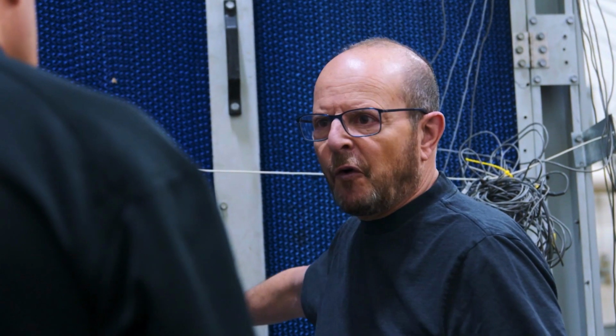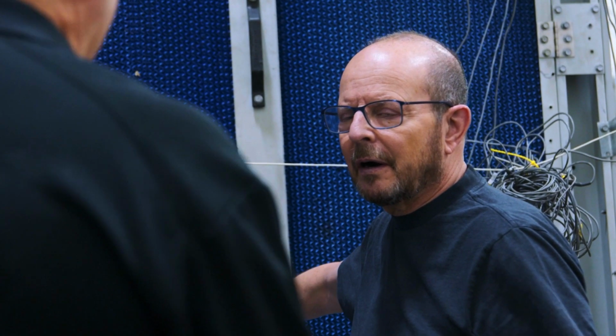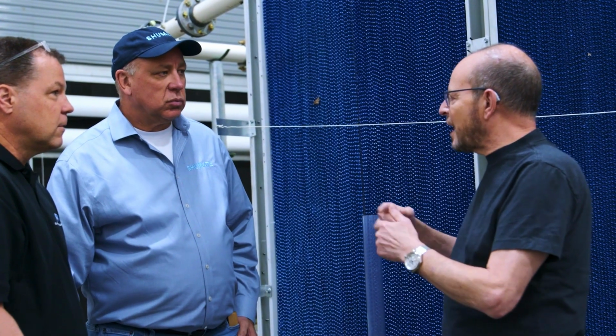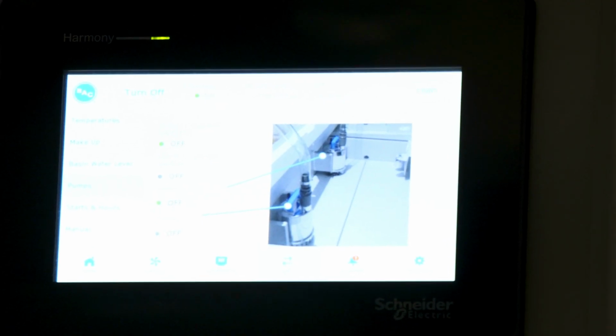As we only really need water with the Trillium product when the ambient temperature gets above 82 degrees Fahrenheit or 81 degree Fahrenheit wet bulb. So we're basically cooling the data center dry without water all the way up to 82 degrees Fahrenheit, and we're only using water for about 10% of the year. We're here to see if the machine really works. And what we've seen so far is quite promising.